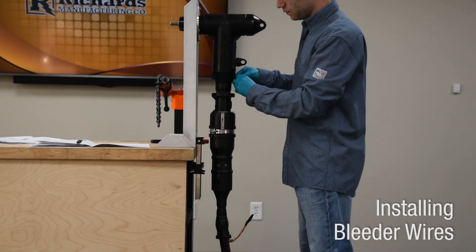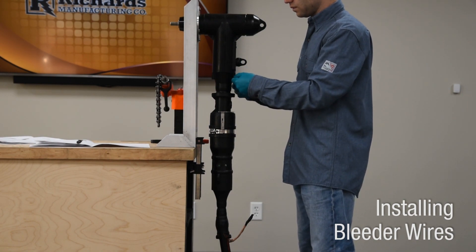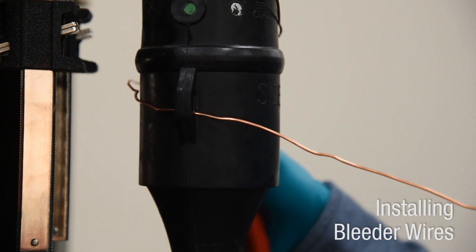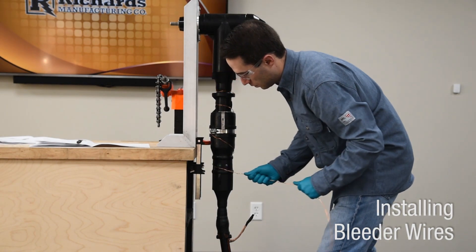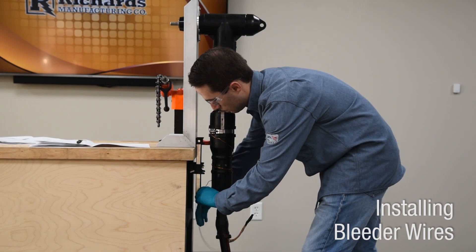Connect copper bleeder wire to one or more of the available eyelets on the deadbreak elbow, extension adapter, and sleeve. Connect bleeder wire to cable neutral and ground according to approved practice. A number 14 copper bleeder wire is included in the kit.